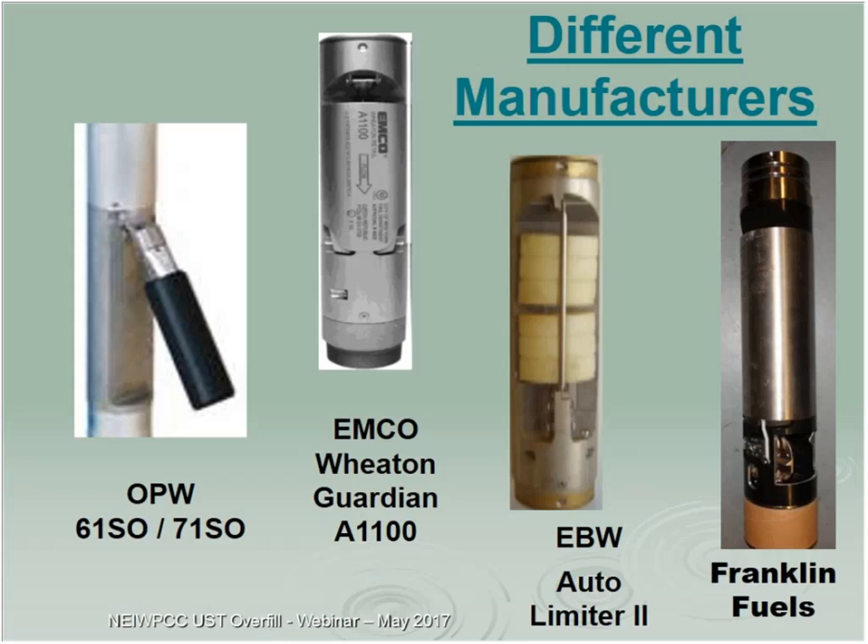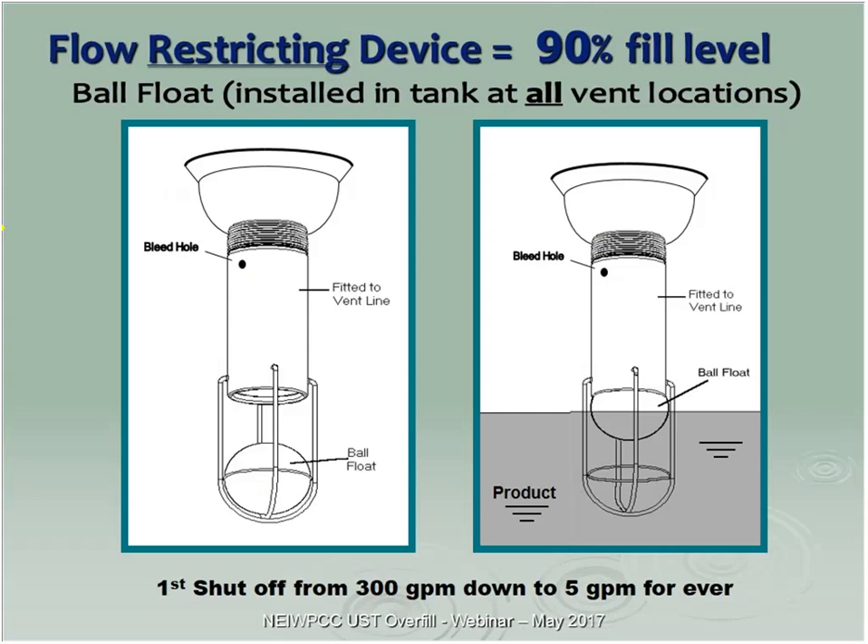Typical manufacturers include OPW, EMCO Wheaton — this one has two floats: a primary shutoff and a second-stage shutoff. Franklin Fuels is also a two-stage device. The ball float sets off at 90%, closing from 300-400 gallons per minute down to just 5 gallons per minute through a bleed hole. There's nothing to close off the bleed hole, which is why we call it only a restrictive device.